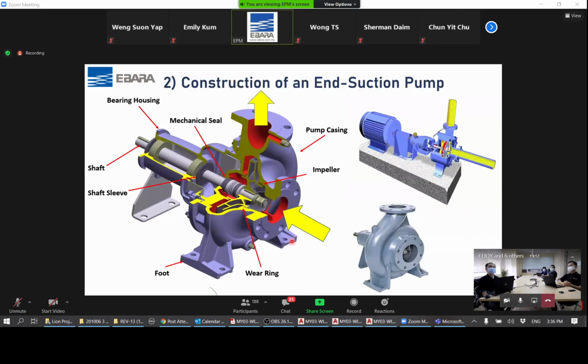Okay, unlike a vertical multi-stage pump, which is made out of pressed steel, an end suction pump is made mainly from cast iron to achieve a very strong and robust casing. And this is able to withstand high pressure and dynamic stresses. Now, you can see from the cutout of this pump, the elements are pretty simple. You have the pump casing in front, and there's always a bearing housing at the back of the pump, and that's where the bearings are.